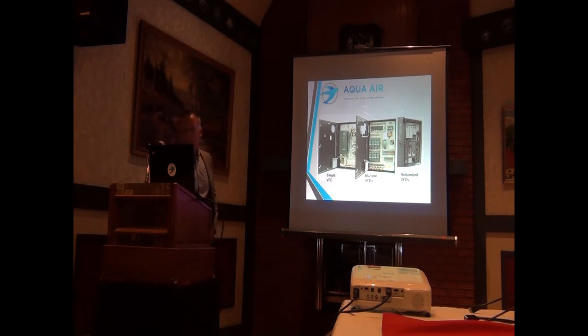Contrast that to a single VFD with a giant motor, say a 100 horsepower, 125 horsepower motor. If that fan goes down or that motor goes down, now it could be an emergency situation if it's at the extremes. If it's minus 30, it doesn't take long for the pipes to freeze and burst. And if you have a more critical environment, say you're a hospital or an old age home, it could be a life safety issue too. It doesn't take long for minus 30 to freeze everything.